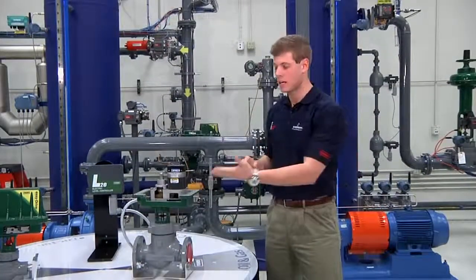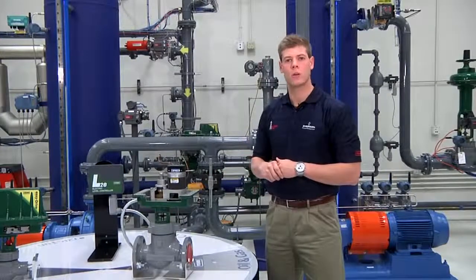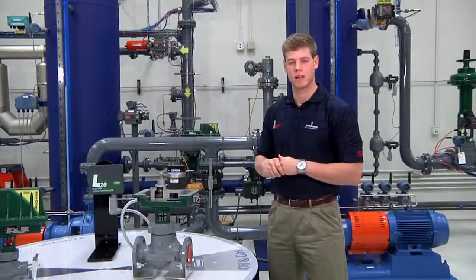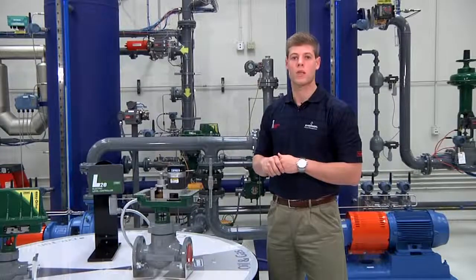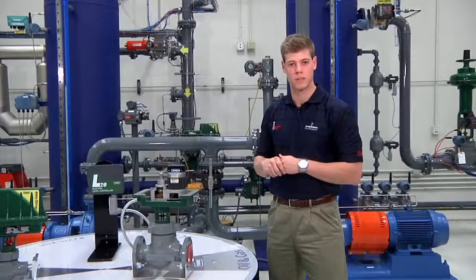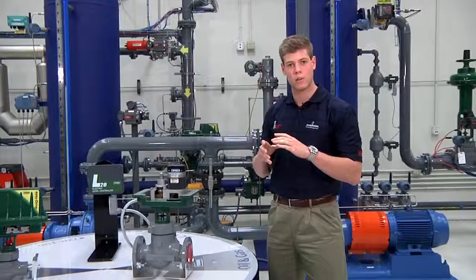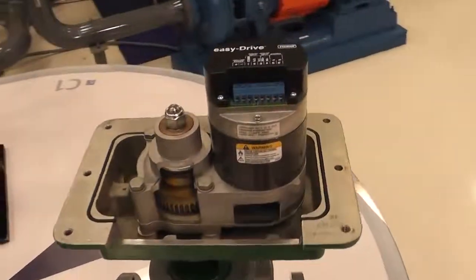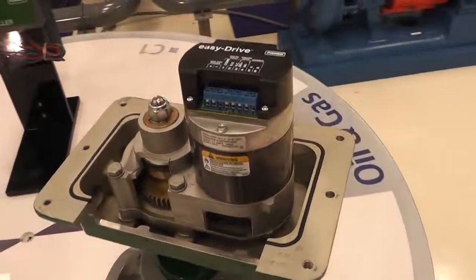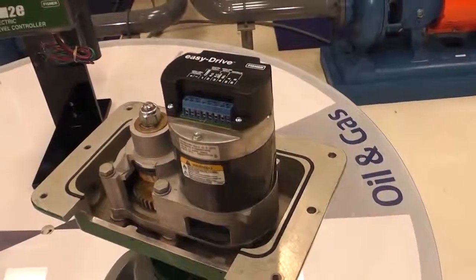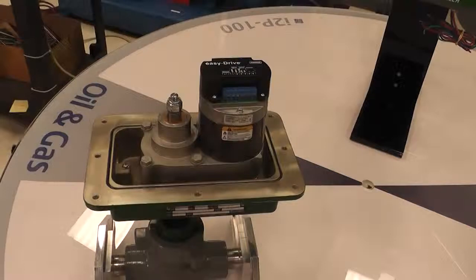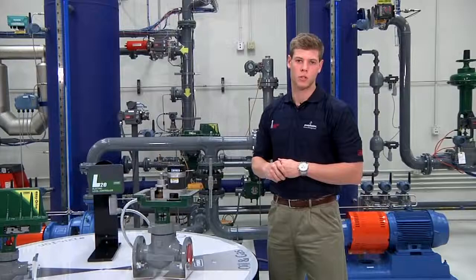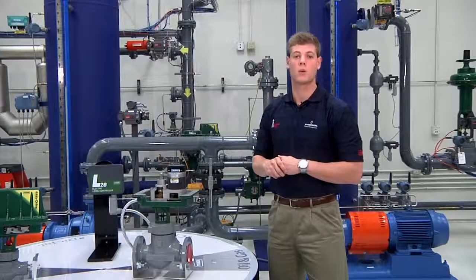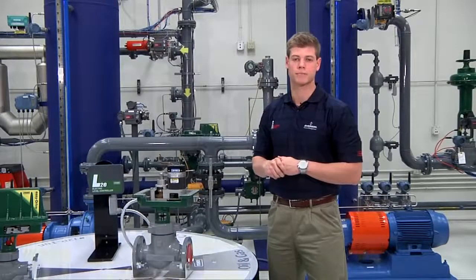As you can see, on the inside of the actuator casing, there is little exposed wiring and all the moving parts are enclosed within the gearbox. For demonstration purposes, we have cut away part of the gearbox on the D4 assembly. Here you can see that the interior of the gearbox is clutter-free and rather simple. Units leaving the factory will not have these cutaway sections. As seen on the D3 assembly, each gearbox is sealed and contained. This intuitively designed interior and gearbox assembly allows for quick installation, setup, and calibration.